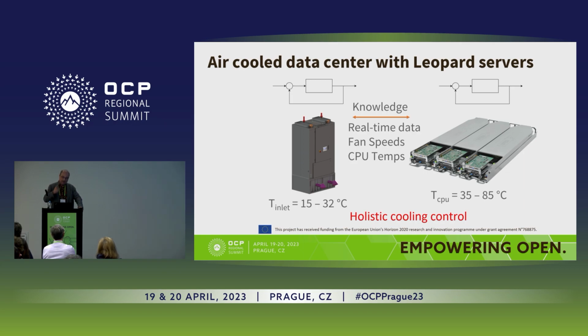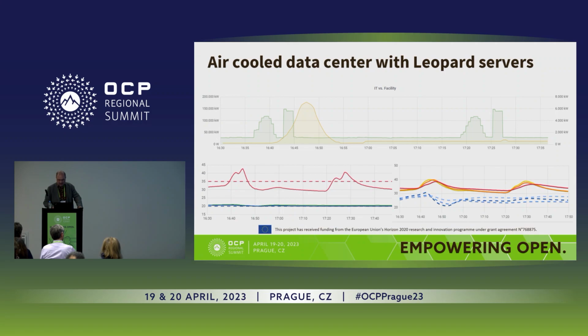Because the air is recirculated in the data center a lot, and the humidity drops to around 3 to 5%. It's not a problem, really, to be honest, unless you're going into the data center and touching surfaces, and then it can be a problem. There's a control system on the servers, which manages the fan. So basically, the idea is to allow a real-time data exchange between the server and the coolers to produce this holistic cooling control. Here are some results.